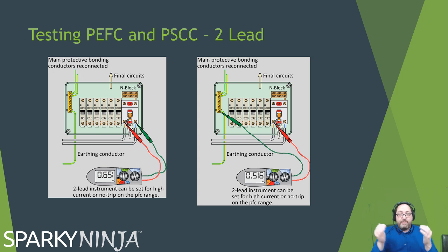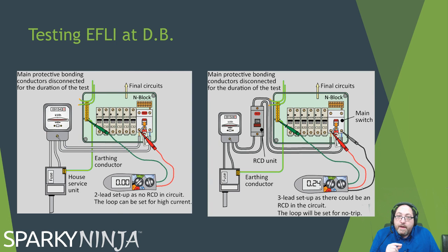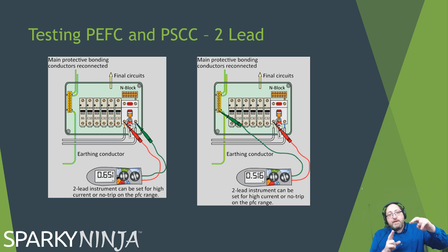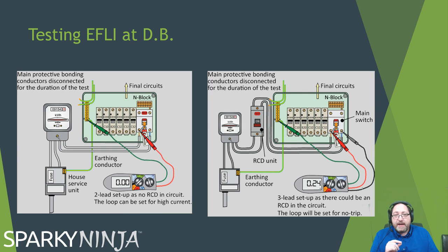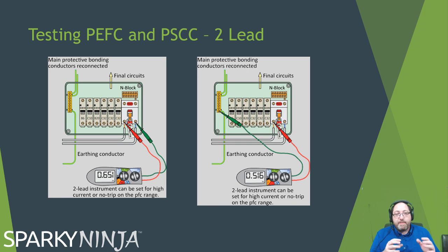I've got the board cover off, but I must, as you'll see here, difference between that one and that one, the parallels have gone back in. The bonding has gone back in. The circuit protective conductors have gone back in. So you're going to do the measurement again and switch it from the loop reading to the PFC reading. You must retake the reading. If you do this reading here and you get ohms and you then press the button that gives you PFC, you can't use that because you have to retake the measurement with the parallels in.